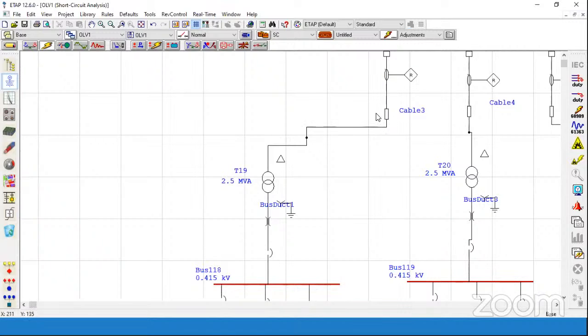For this, we need to calculate the through fault stability or inrush current condition of this transformer. Inrush current condition means during the starting of the transformer, the relay should not give a tripping command or de-energize the transformer. So we need to ensure that during the starting of the transformer, the relay should not detect this inrush condition as a fault condition. Now let me go with this formula of calculation.